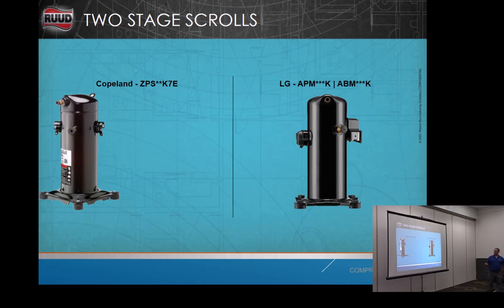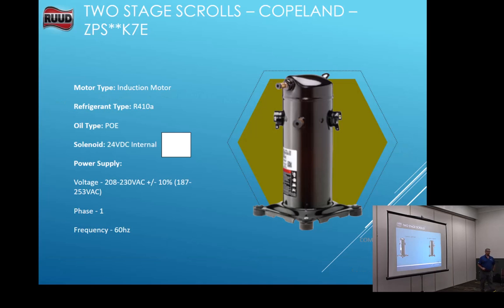Keep that in mind. The LG now, it has a 24-volt external solenoid. It plugs in right here. It's just like a little solenoid that goes to your reversing valve. Comes off of the board, goes there, sends 24 volts when it wants to energize it. No big thing. So it's external. Same compressors, basically 208, 240. The Copeland has a 24-volt internal solenoid. So there's our suction funnel that we talked about that you've seen there in the pictures in front of you.